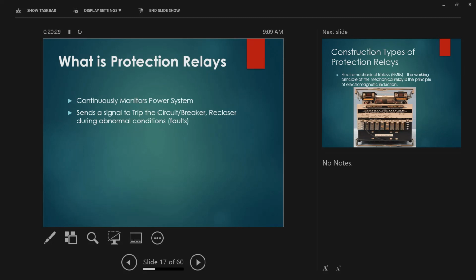Anyway, what is a protection relay? As we said earlier, it continuously monitors the power system, day and night. Load or no load, the relay should be there. Another function is to send a signal to trip the circuit breaker or recloser during abnormal conditions. That's why if you're a breaker technician, you're looking at the speed of your opening time, the speed of your closing time, and if your closing coil is okay. All of this matters because of the speed of clearing the fault. Say the breaker opening is 50 milliseconds or 30 milliseconds, you have to add that to the speed of the relay, how the relay processes the fault algorithm internally, and it will add up together. So let's say an average of 75 milliseconds to clear the fault. That's very quick. I think that's the standard today, which is ideal anyway. So that's why we're always dealing with time. The accuracy of that is required for us to meet the requirements of how the protection relay protects the system.